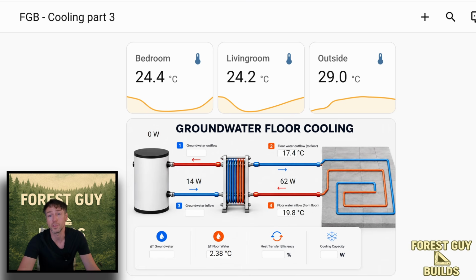The temperature difference is also not constant. Yesterday evening and during the night, when the floor still contained much more heat, the temperature difference between the water entering and leaving the floor was even larger. At one point the difference was more than 3 degrees Celsius.